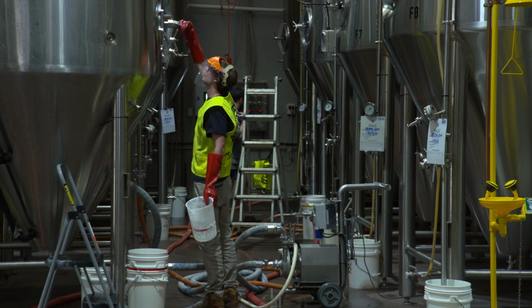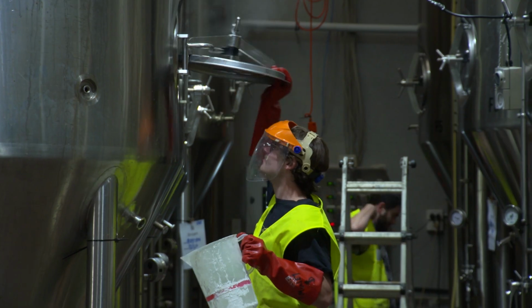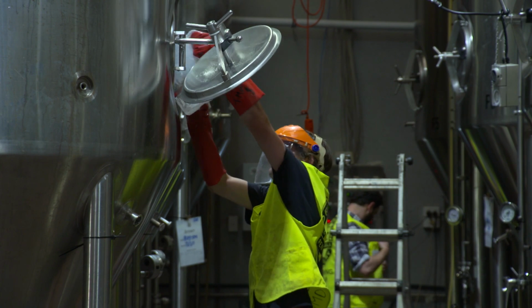Mornington were exceeding their supply capacity of about 80 amps a phase. And traditionally, in order to increase that, you would need to go and apply for a mains upgrade for the facility, and that can take anywhere between 6 to 18 months to actually get done. So most breweries would rely on a generator, and a generator is like either a generator or mains solution. The generators very rarely run in parallel with mains, and particularly here for the brewery, that meant that they would be running generator for 24 hours a day, really until March or April when the seasons started to get cooler.